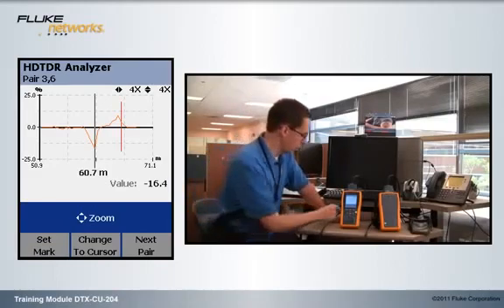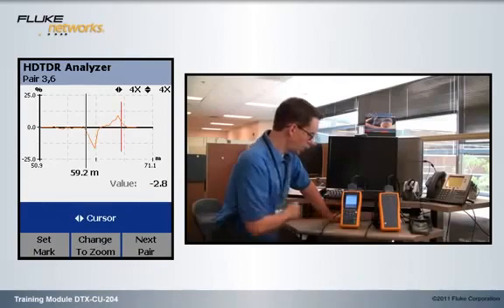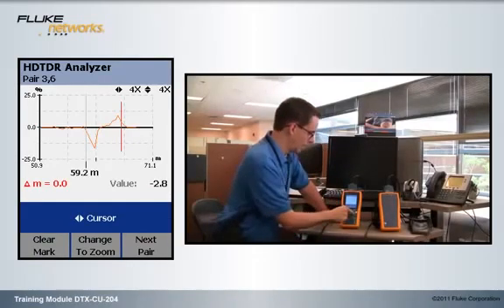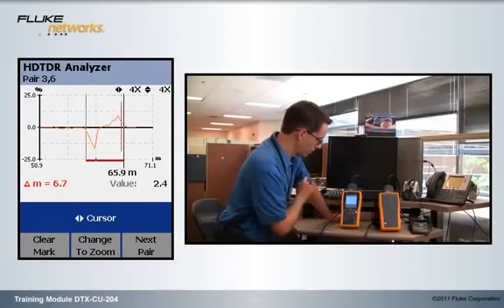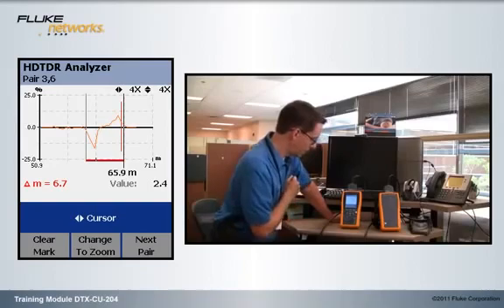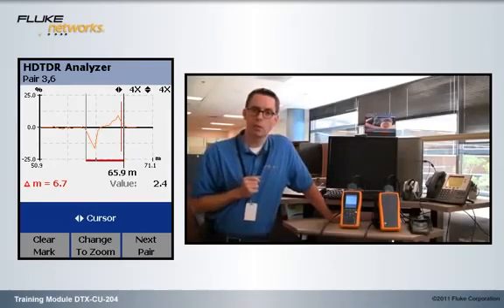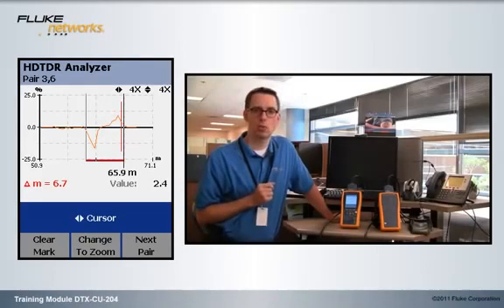So, here's what we can do. We'll take it off zoom mode. We'll move the cursor to where this starts. We'll set the marker, and then we'll move to where it ends. I would say roughly about there. Indicating that we have about 6.7 meters of cable at the end of the link, which has water in it.